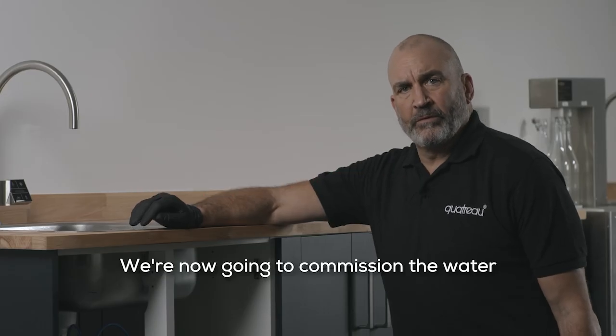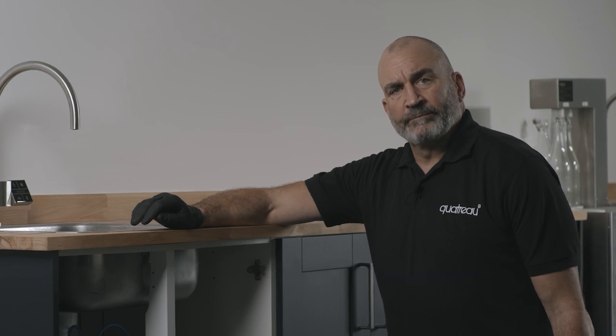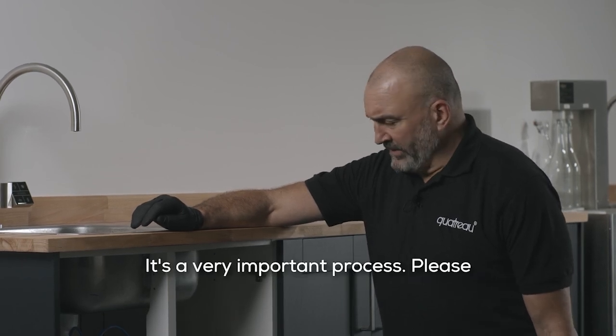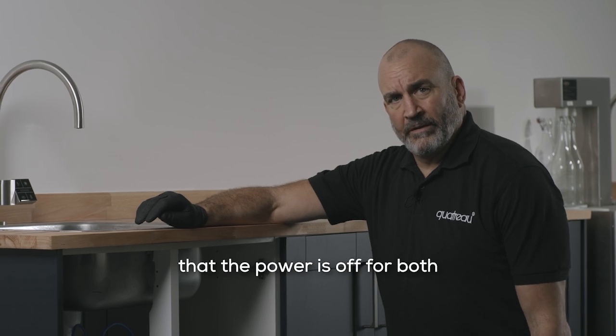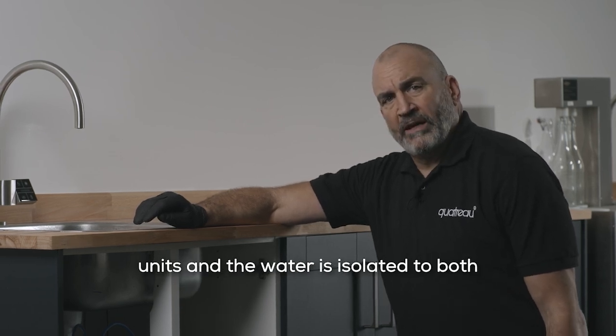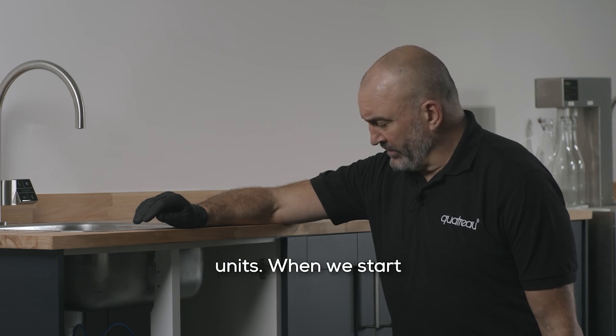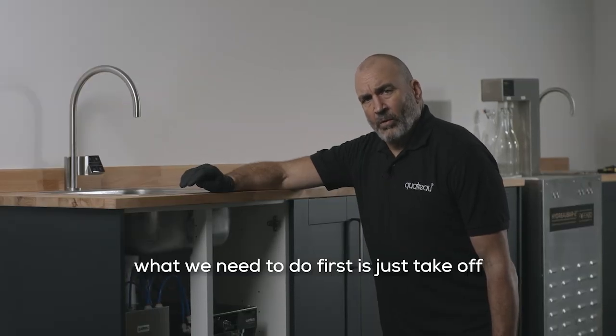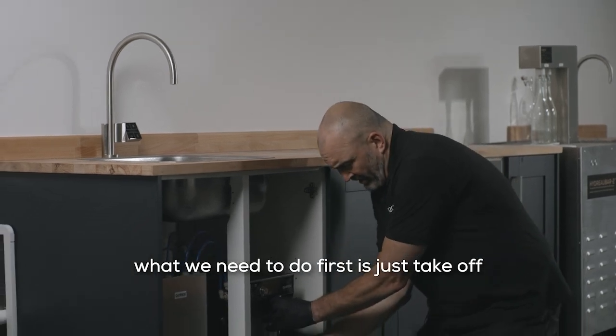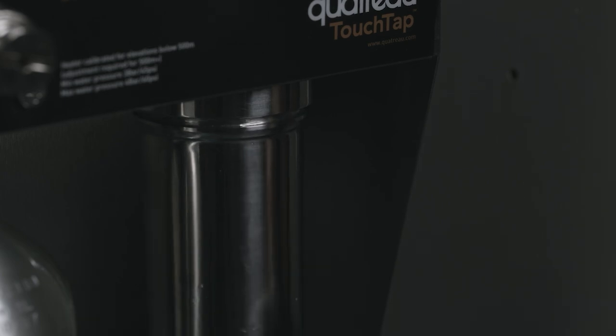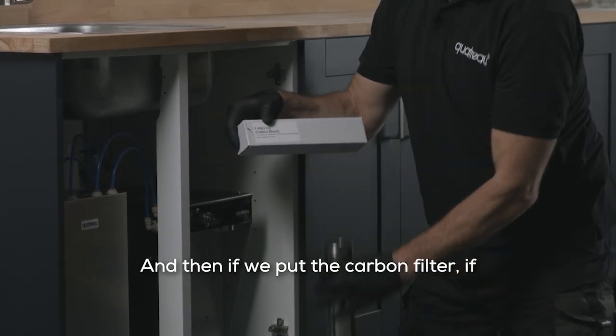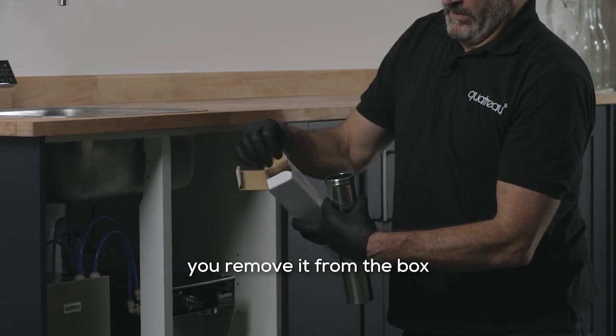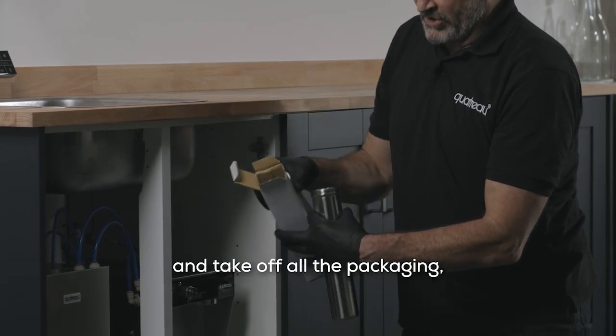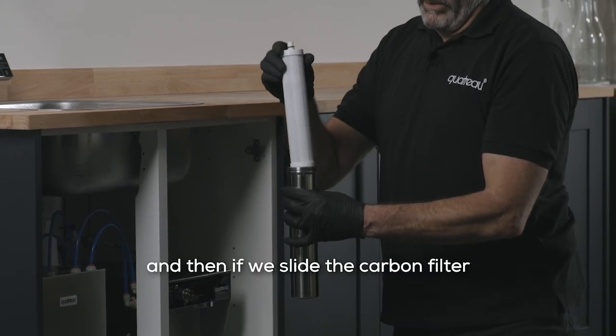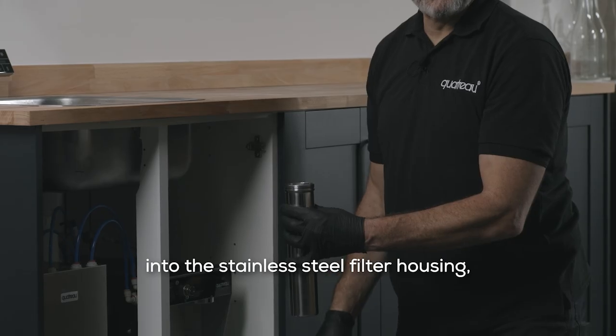We're now going to commission the water heater control unit and the chiller. It's a very important process. Please make sure before you start that the power is off for both units and the water is isolated to both units. When we start the commissioning process, what we need to do first is just take off the stainless steel filter housing from the front.